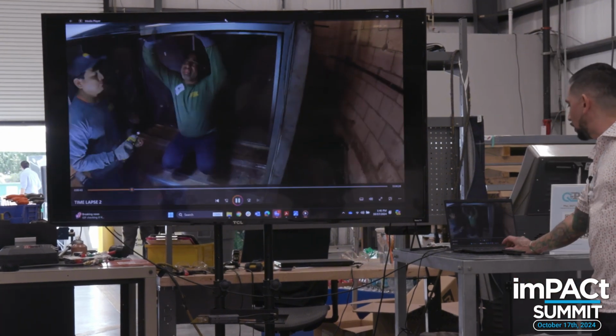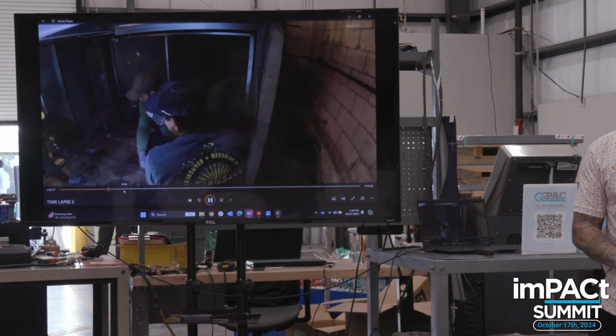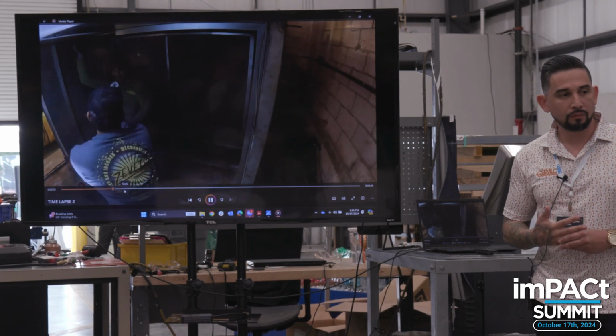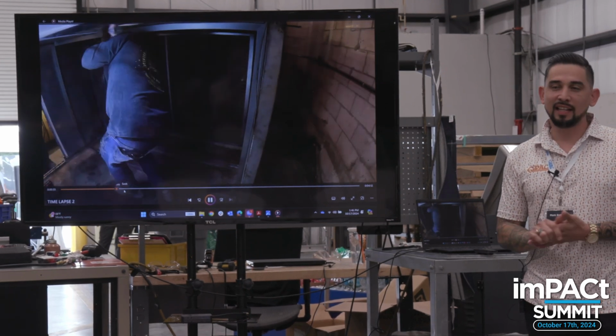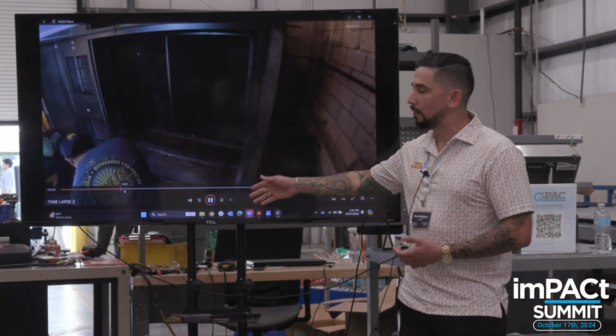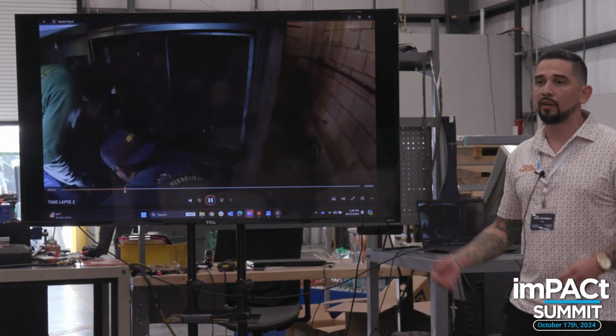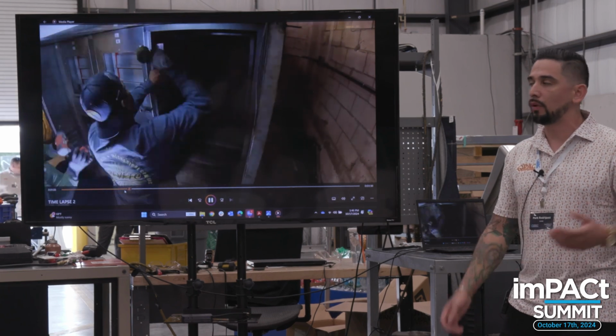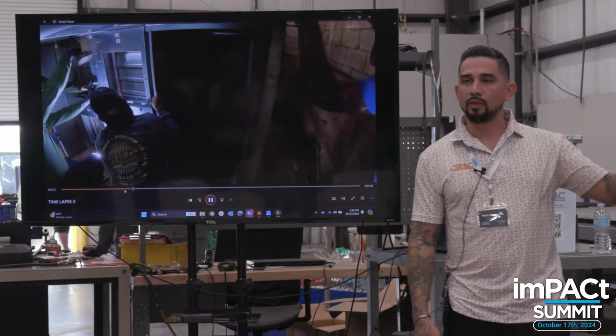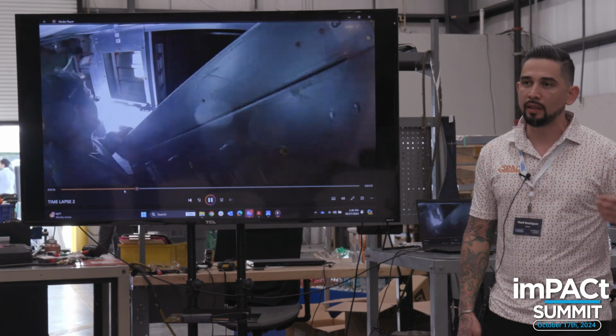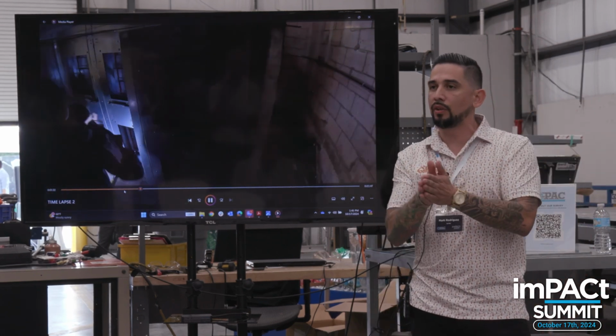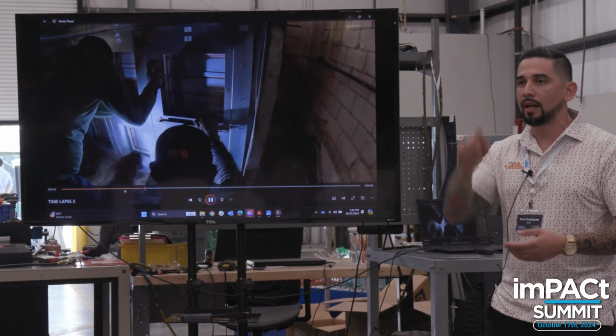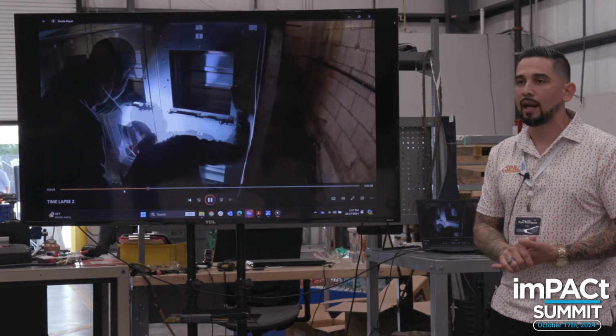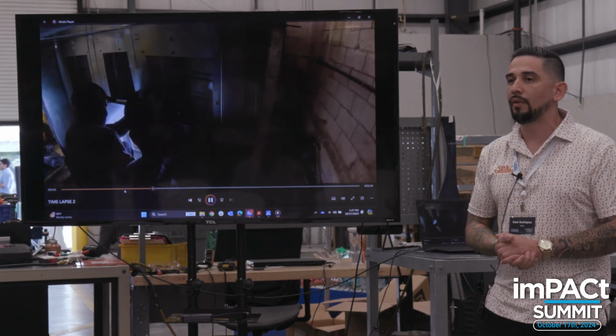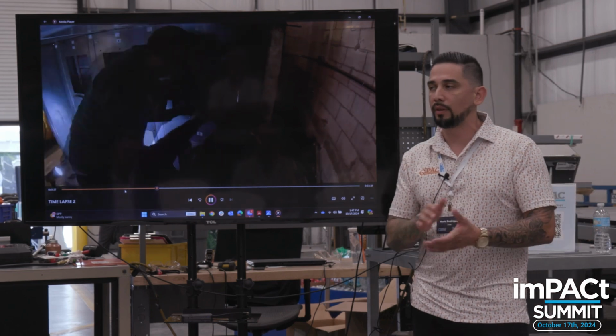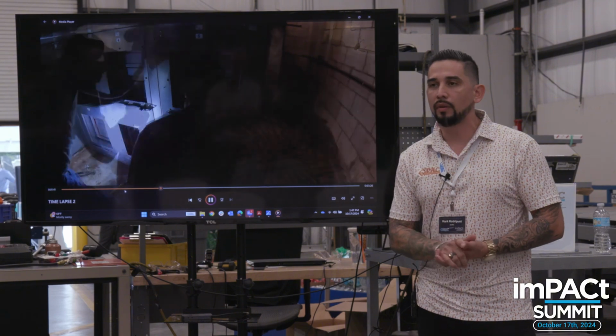Contractors sometimes have to notch or cut slightly because it's never a perfect rectangle, there are angles involved. That's not uncommon, it's a common modification needed when the perimeter angle won't fit perfectly. We're not there to help decide what to notch, cut, or extend, you have to handle that yourself. I've been to a few site visits where the perimeter angle wouldn't sit where it needed to, so we had to install another flat bar to extend it. There are hard connections or unions in the unit you can't remove or notch out, so you have to notch the bulkhead around them. There are times you'll have to think on your feet, because we can't account for every notch needed for the Q-PAC installation. But there's always a solution, and we can always make it work.